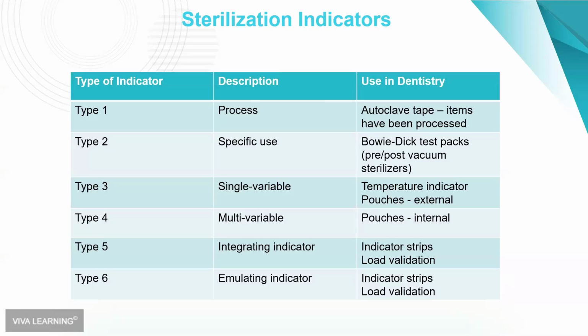And the best example I can give you is a Bowie Dick test pack that's used on a daily basis if you have a pre and post vacuum sterilizer. A lot of people don't realize that if you have one of those vacuum sterilizers, you need to run and document this vacuum test every day. And then it also has a sterilization indicator. Type 3, which is the very common external indicator on a peel pouch, is a single variable. It's typically temperature, okay? Type 4 is a multivariable, and it's the internal indicator on your pouch.